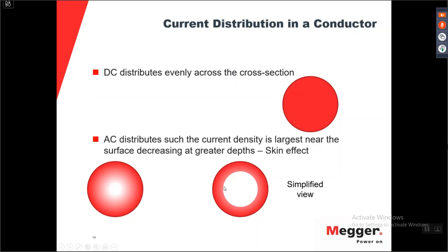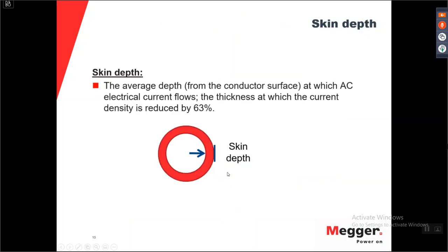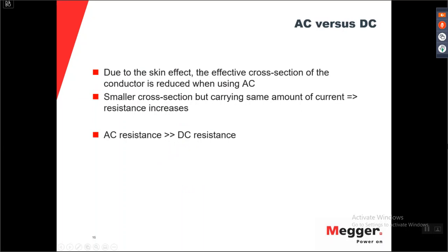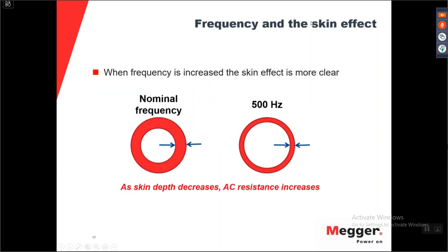Here we can also, when we look at it in the simplified view, define this skin depth, which is the thickness at which the current density is reduced by 63%. So, due to the skin effect, the effective cross-section of the conductor is reduced when using AC. A smaller cross-section, but the same current, gives an increase of resistance. Hence, the AC resistance is always larger than the DC resistance. If we then look at the frequency and the skin effect, what will happen is when the frequency increases, the skin effect becomes more clear and the skin depth is smaller.